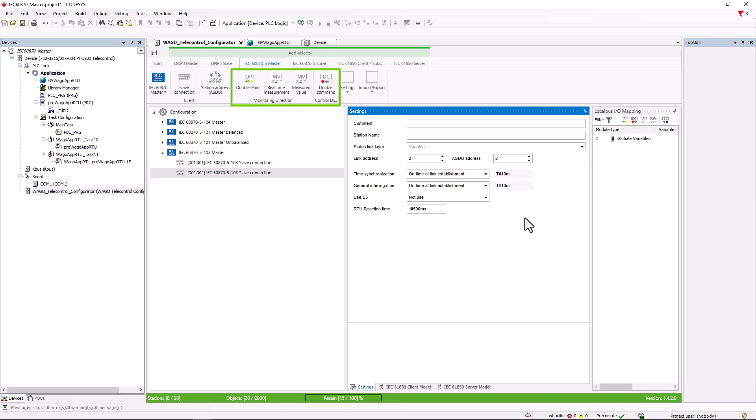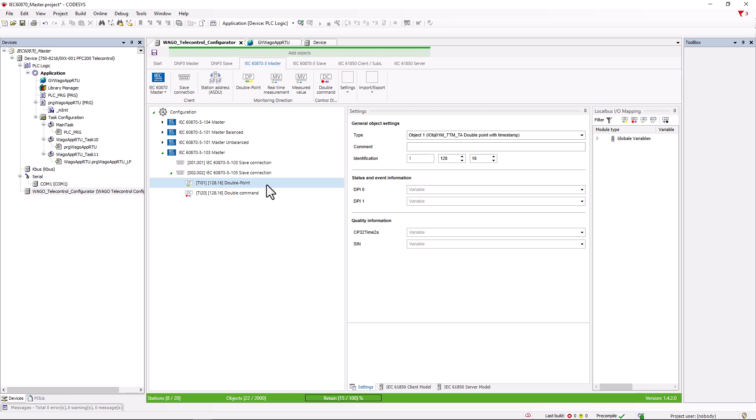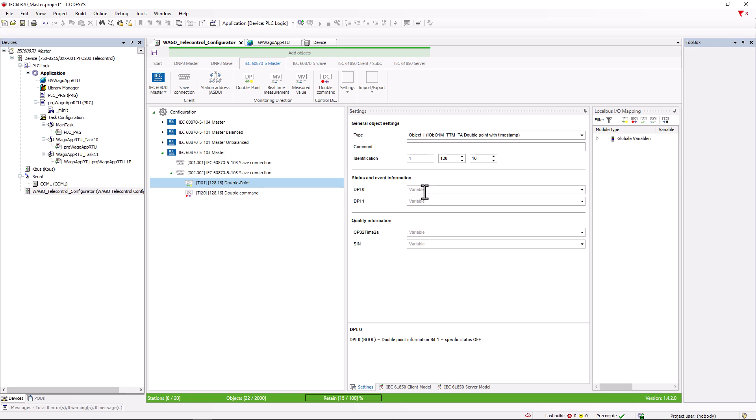This practice has become so widespread that in some cases only one address is documented. If we now look at the data points, we can see that there are far fewer to create than with the other protocols. For example, with bool data points, we only find the double point information in the signaling direction and the double command in the command direction. Some protection manufacturers refer to single point information or single commands at this point in their documentation. This means a double point information or a double command where only the first bit is used.